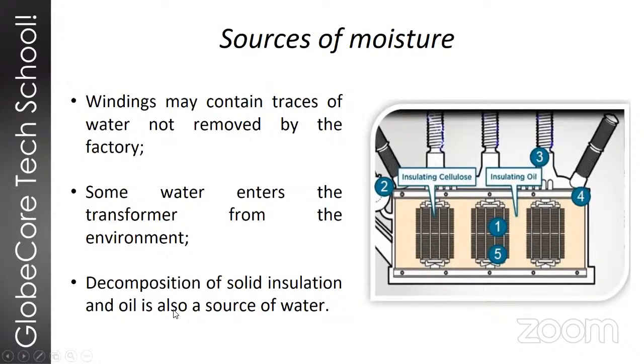The third source of moisture in the transformer is intrinsic. It's internal, basically. When cellulose and oil age, when they oxidize and their molecules break down due to all those chemical processes, all these chemical reactions, or most of them, emit water or form water. So especially if the temperature is high or if the insulation system is significantly worn, this will be another source of moisture in the transformer. Okay, next slide, please.